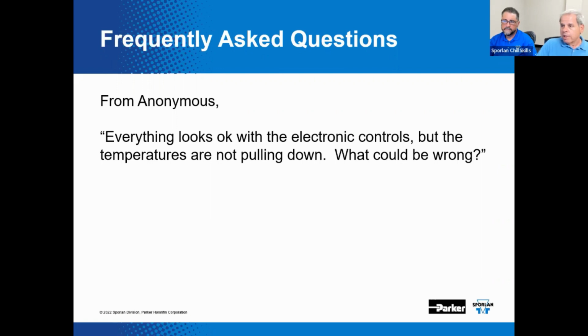It's from Anonymous. Everything looks okay with the electronic controls, but the temperatures are not pulling down. What could be wrong? John, what could be wrong here? Well, in this case, there are a lot of different things that could be going on. You want to make sure the rack is properly powered up and running at a sufficiently low suction pressure to achieve the desired evaporator coil temperature. You also want to check the operation of the liquid line solenoid. You might want to make sure the correct refrigerant is in the system. That's a big deal.